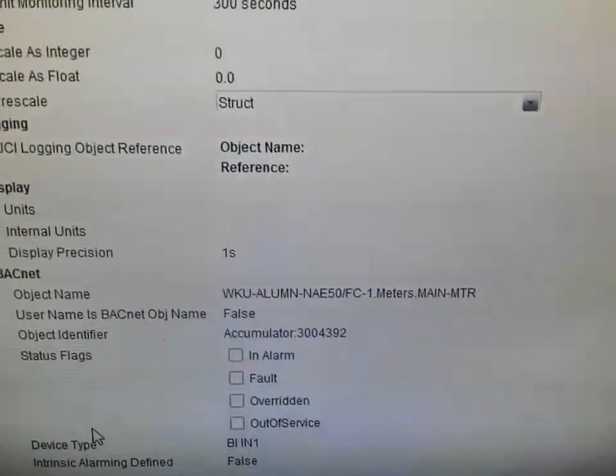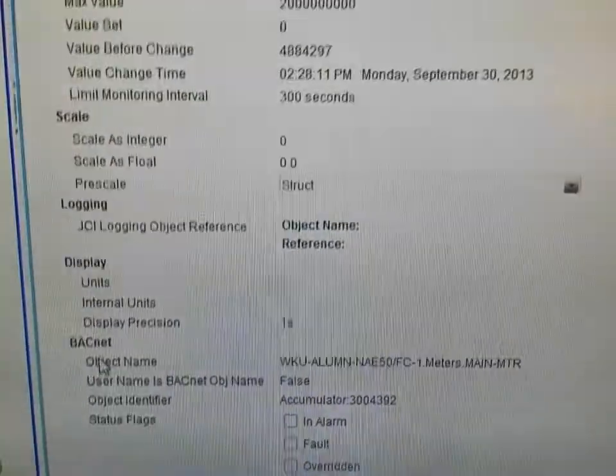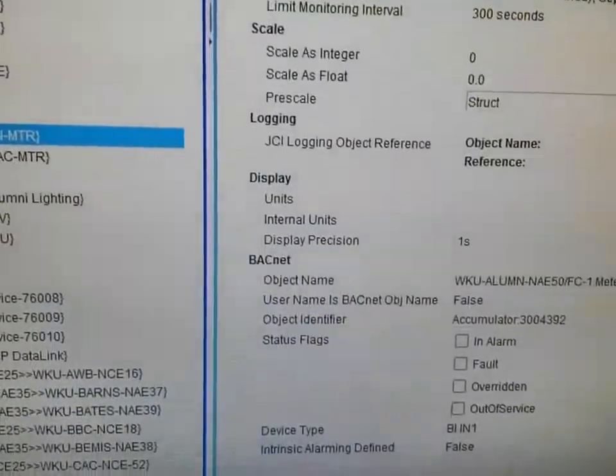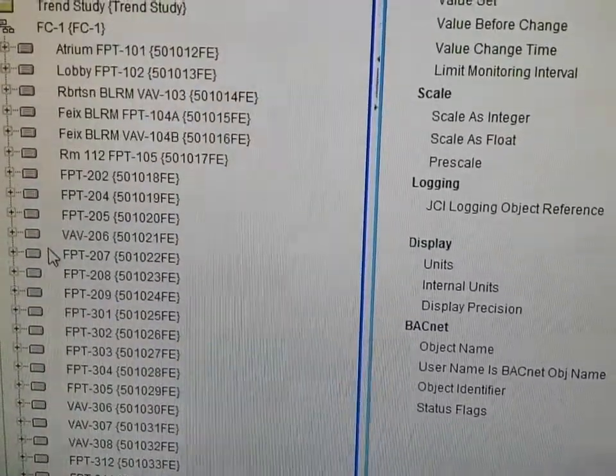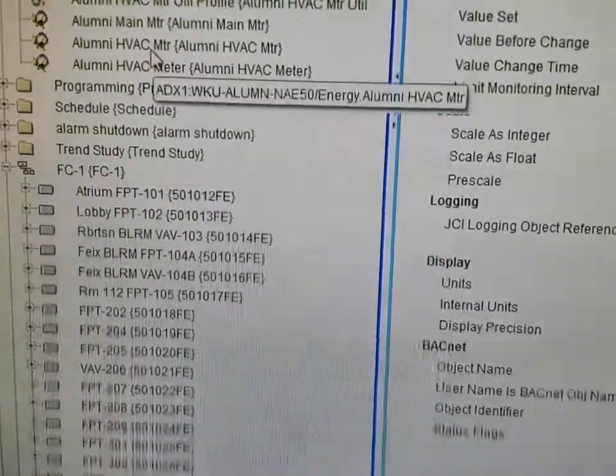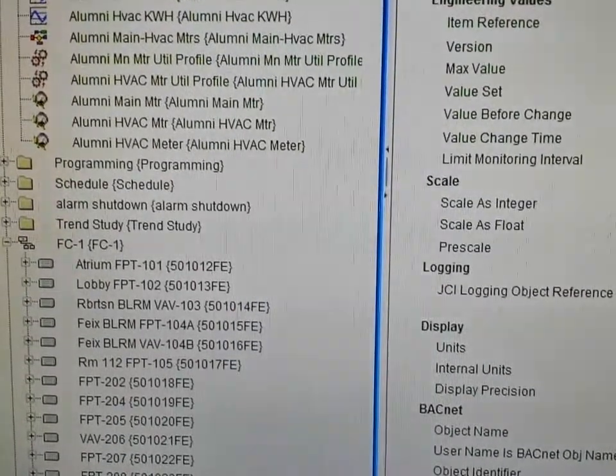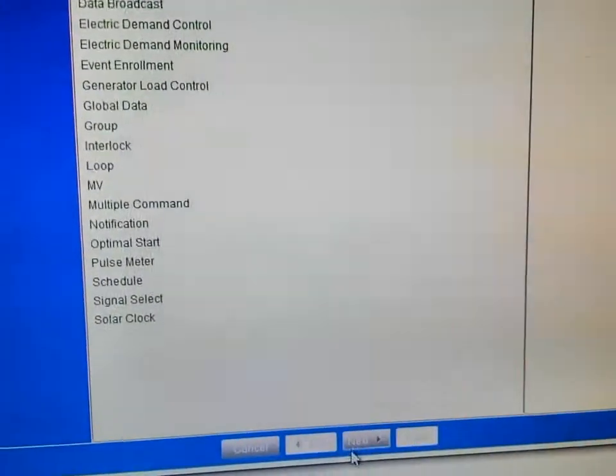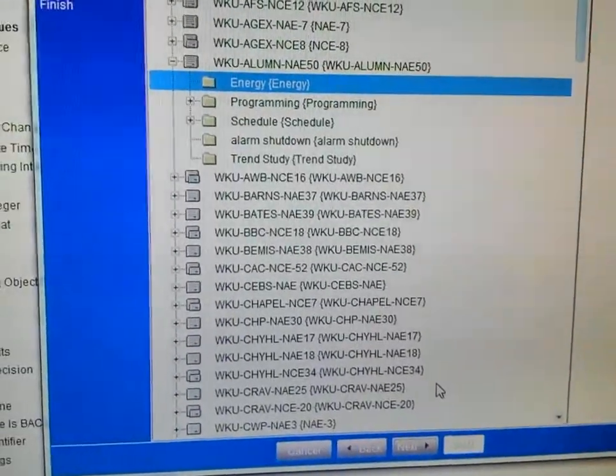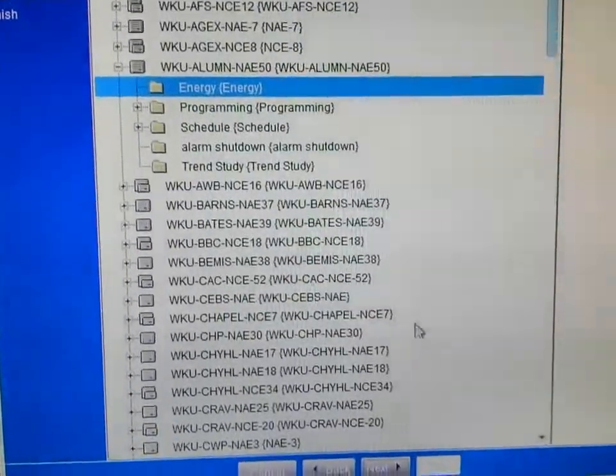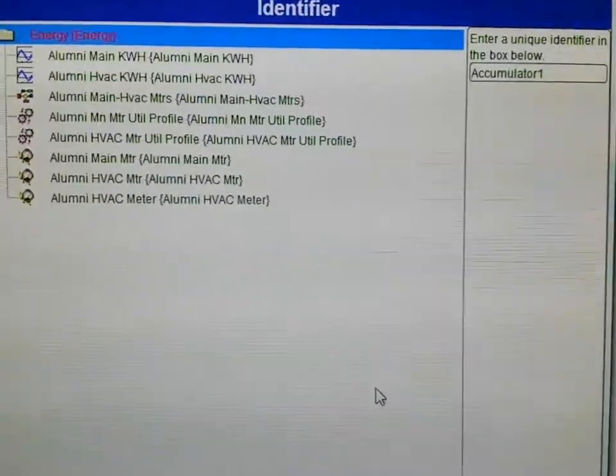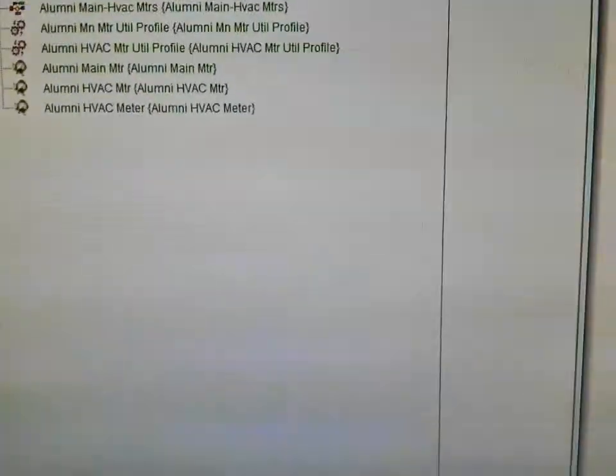What we're going to do here is look at one that is configured internally to the device. However, the setup is pretty much identical if you were to do one under Metasys extended architecture. If you're going to install your meter, the first thing you would do is tie that meter to an input point on your controller, and then somewhere in your programming folder or under your NAE you would insert an accumulator. The accumulator object basically keeps gathering information every time the contact is closed on that input — it rolls up to the next value and stores that information.